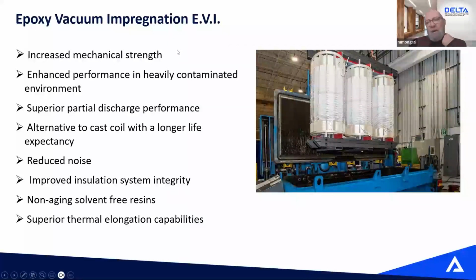So at Delta, we do vacuum impregnation of our transformers in a vacuum chamber, and we use epoxy. We don't use just plain varnish. We don't use polyester resin. We use epoxy. Why? Because epoxy is the best coating material you can use to protect your transformer. And we don't do the vacuum process just on the windings. We do the vacuum process on the entire core and coil.